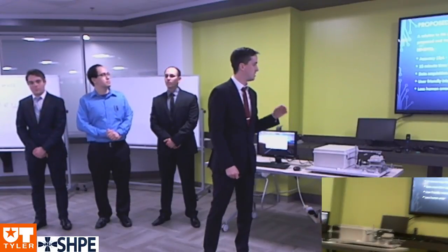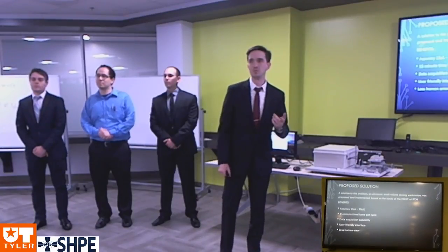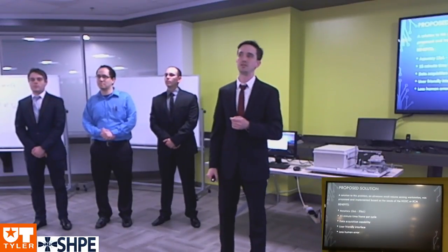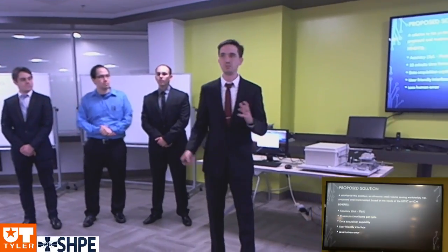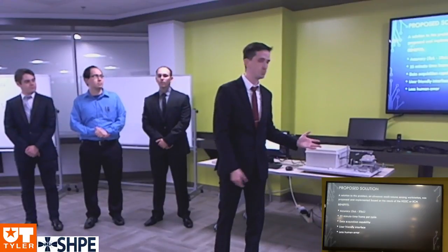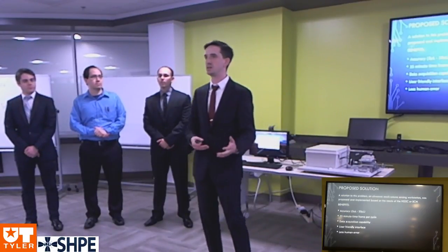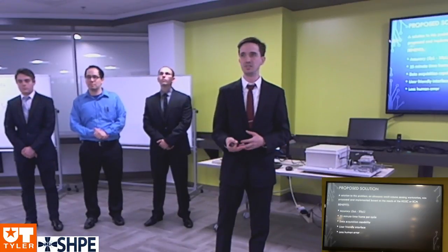So our proposed solution came in the form of an ultrasonic sensing workstation. And basically what we were looking to achieve was 5 to 10 microliter accuracy using an ultrasonic sensor. We wanted something that was able to do that in about 15 minutes, so this way the technician could place it on this workstation, maybe step away for a minute, come back and have those results be able to be exported simply and easily to a CSV file for further analysis.